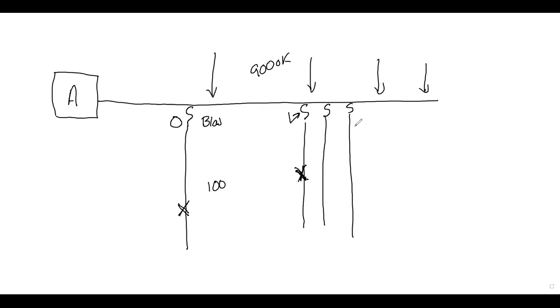Fuses are the most dominant line isolation device out there. We also fuse all our transformers. Think about it: if an animal gets up there, or the transformer gets struck by lightning and starts burning up — without a fuse — you'd take out the entire feeder circuit for the sake of one transformer. That's why we fuse all transformers.